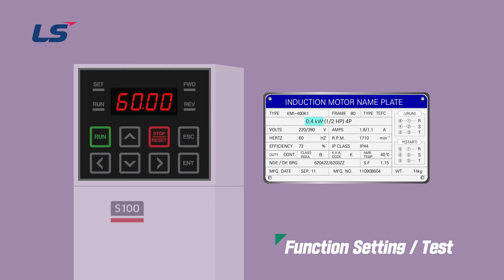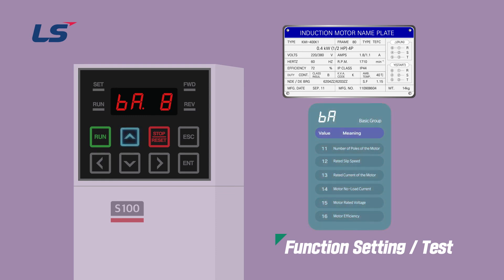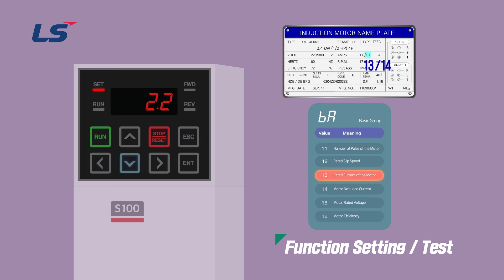We will input parameters based on the motor nameplate information. For capacity of the motor, select DR group number 14 and input the appropriate capacity. Items 11 to 16 of group BA are the number of poles of the motor, rated slip speed, rated current of the motor, no load current of the motor, rated voltage of the motor, and motor efficiency, respectively. Enter the motor nameplate values in turn. If it is difficult to measure the no load current, input a current value corresponding to 30 to 50% of the rated current of the motor.